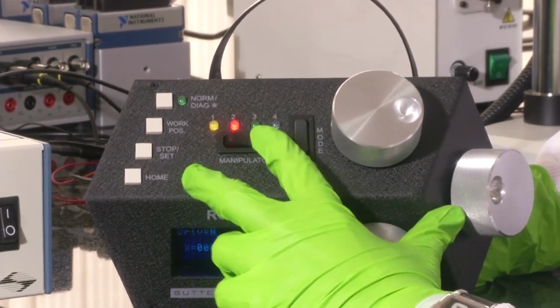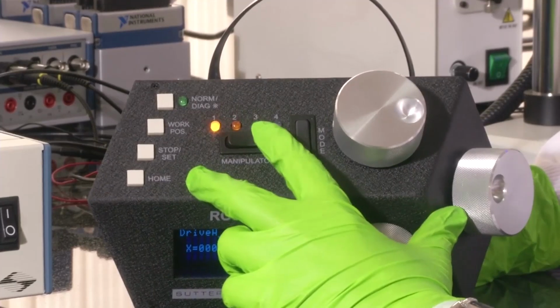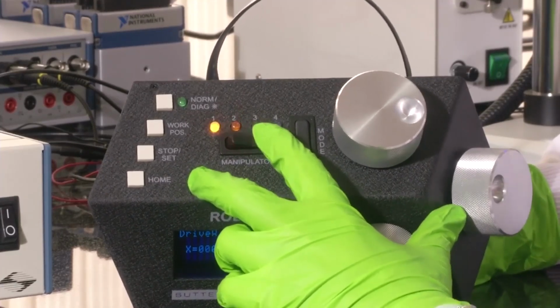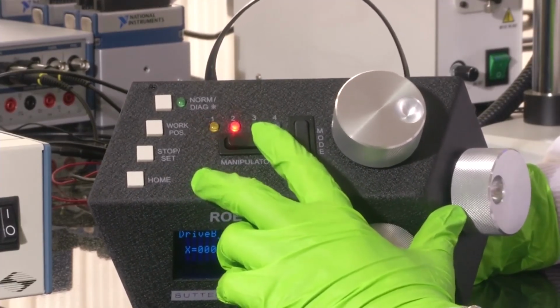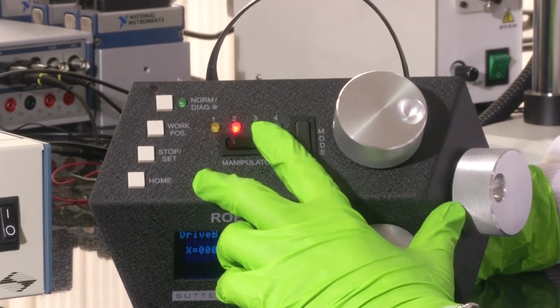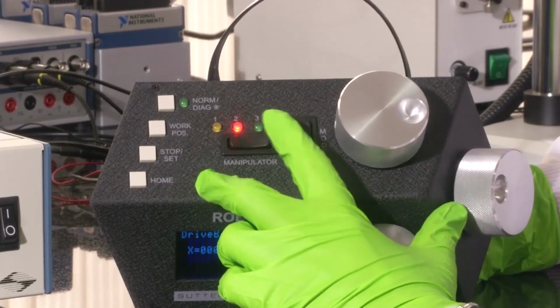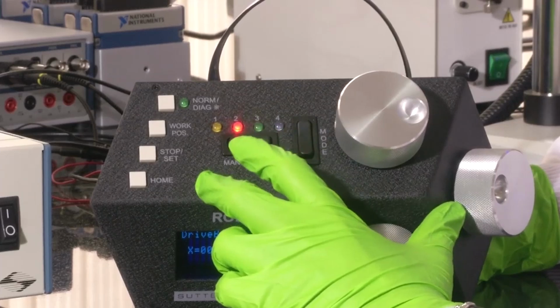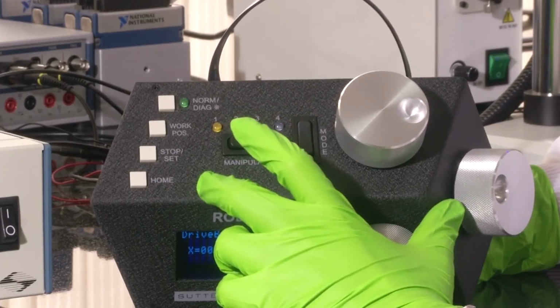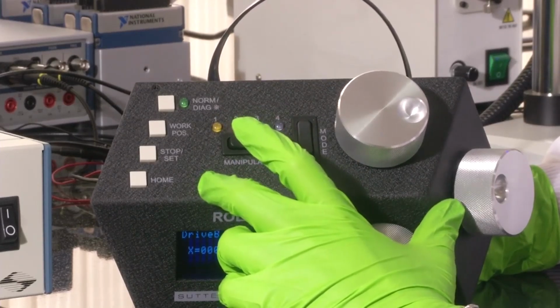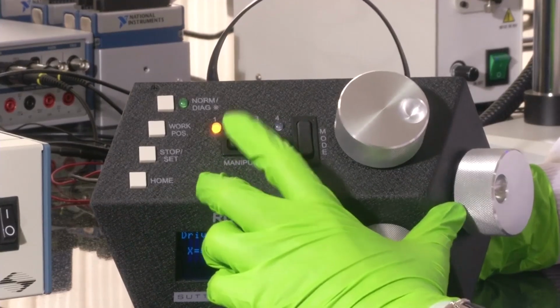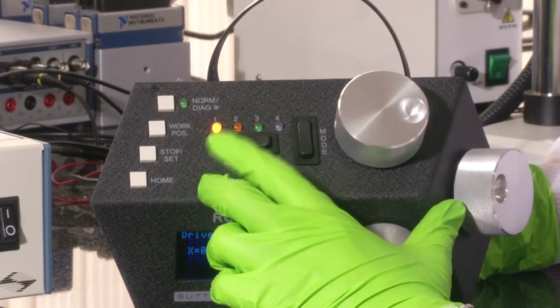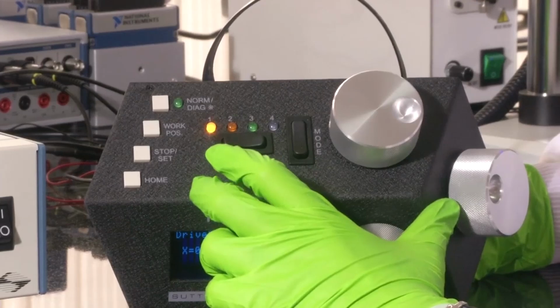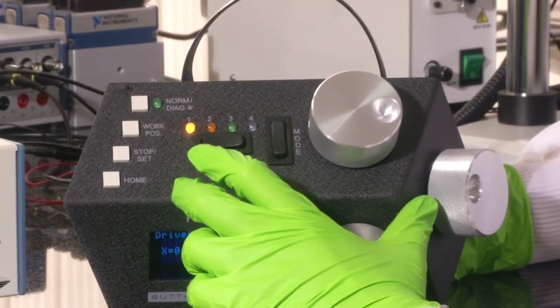So, manipulator 1 and manipulator 2 only make sense, the other 2 are not available. That is why even if you change the mode, it will only switch between one manipulator and the second manipulator. It does not go to the third and fourth because the system has not detected extra manipulators connected to it. So, that much intelligence is there in the control unit. Right now let us keep it back to controller 1. When you connect to 1, you will be able to control manipulator A.